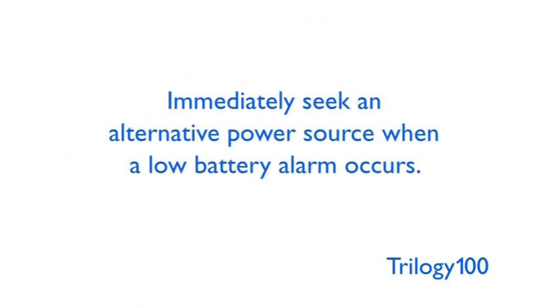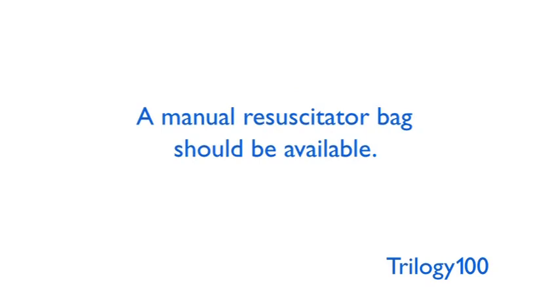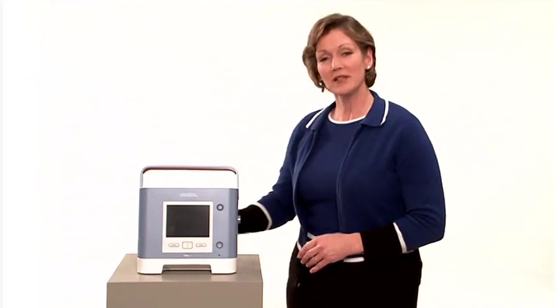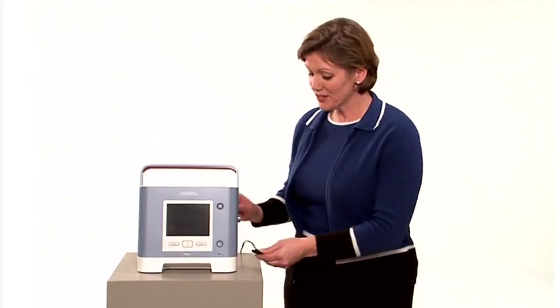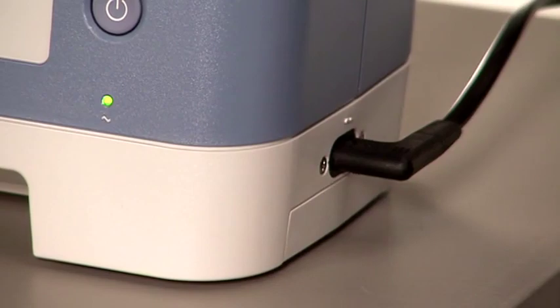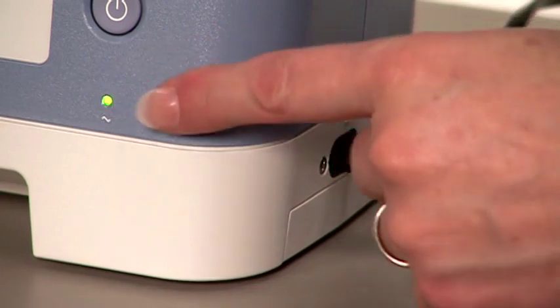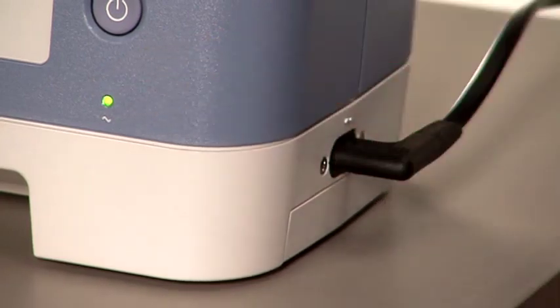Immediately seek an alternative power source when the low battery alarm occurs, because loss of therapy is about to occur. A manual resuscitator bag should be available for use just in case there is no power available. To use AC power, plug the socket end of the power cord into the AC power outlet on the right side of the device. Plug the pronged end into a wall outlet. The ventilator must be connected to a wall outlet that is not controlled by a switch. You'll know that the AC power is connected and the device is operating properly when the green AC power LED on the front of the unit is on.